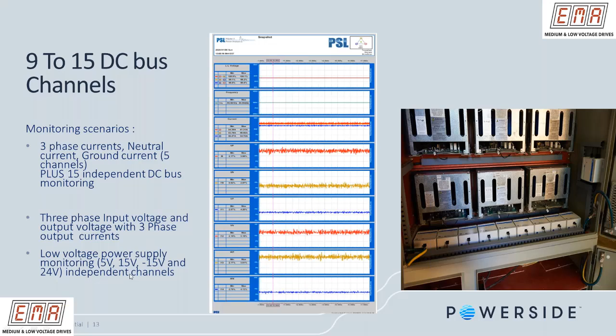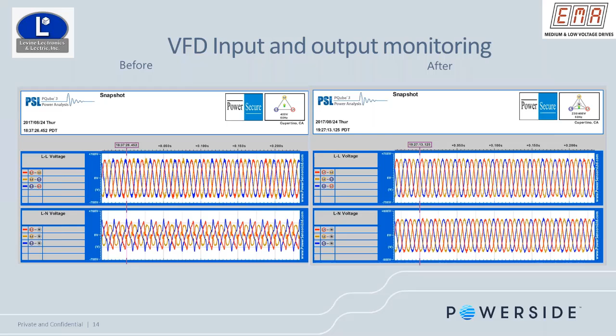Typically, your three-phase input voltage should look like this, and so this looks really good, right? But if we look at our current, we have imbalance here, right? So once the problem is resolved, now we have balanced current, and this is how it's supposed to look. Now, if I log onto this drive scan at the time, I can actually see this, right? And say, okay, there's a problem here we need to address. Could be from the power company, it could be a loose connection or anything like that.